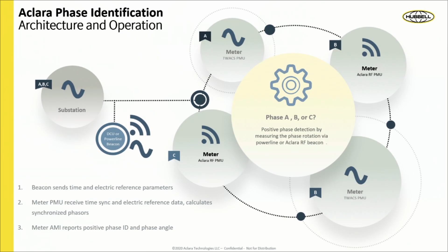This is part of 2.0. As the meters have the capability to identify the phase, you can run phase identification to understand each of the loads, each of the consumers, and which phase they are attached or connected to, which is very important because then you can balance the load and avoid a lot of issues in the network.